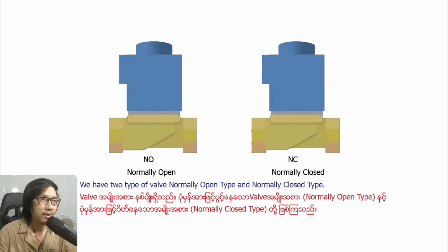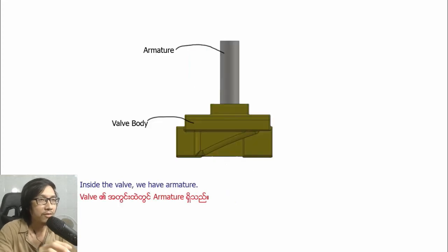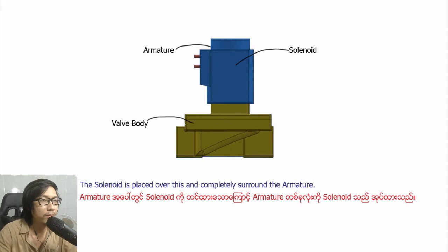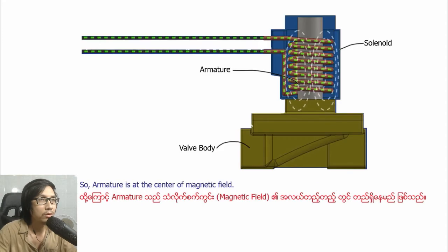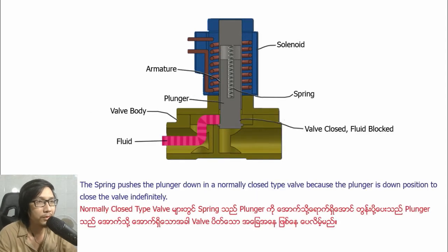We have two types of valves: normally open type and normally closed type. Let's look at the normally closed type first. Inside the valve we have an armature — the solenoid is placed on this and completely surrounds the armature. The armature is at the center of the magnetic field. Inside the cylinder of the armature is a plunger and a spring. The spring pushes the plunger down in a normally closed type valve because the plunger in the down position closes the valve.